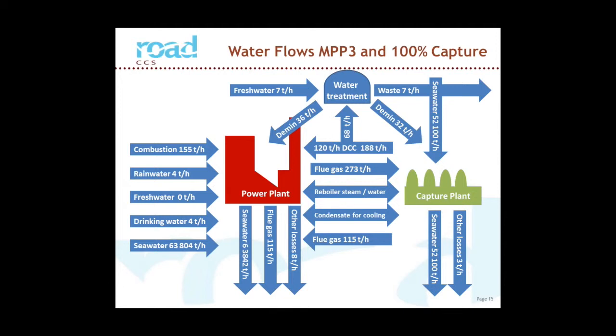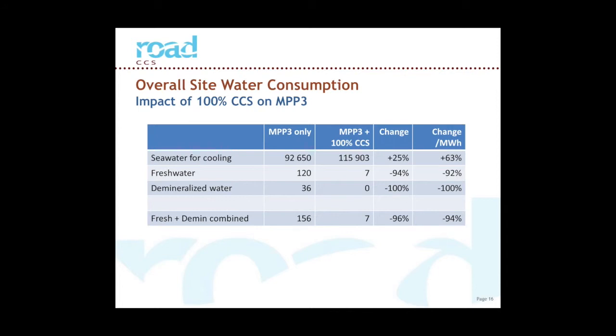So we see the cooling water for seawater demand for cooling has gone up by 25%. That would actually take us above what our existing cooling water intakes can take at MPP3. So if we were to do this, we would need a new cooling water intake, or we'd have to put a cooling tower on or something like that. You can see that the increase in cooling water demand dwarfs the freshwater usage and freshwater consumption. And on a per megawatt basis, 63%, this is a big number. It's partly due to the loss of efficiency in the process, but it's also due to the fact that we're cooling the flue gas down to a lower temperature. So we reduce the heat that's emitted to the atmosphere in the flue gas and put it in the cooling water instead.